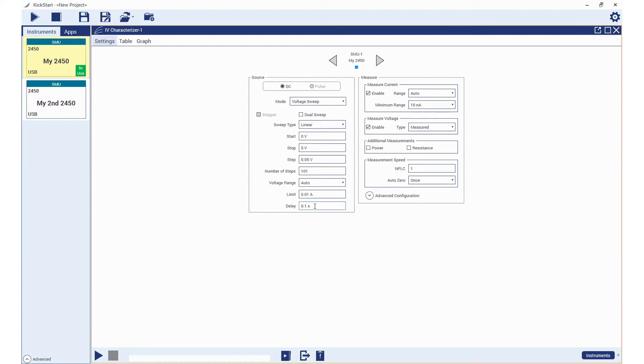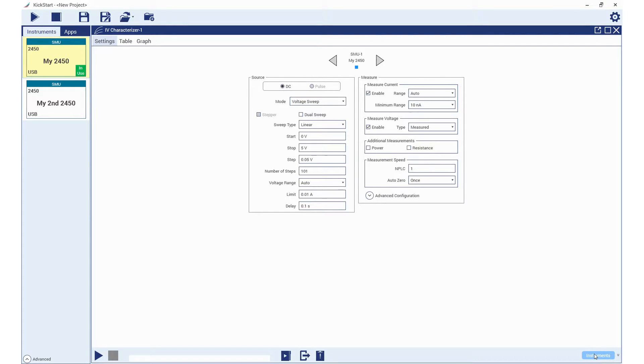We will now add the second SMU by clicking on the instrument icon at the bottom right-hand of the app window and use the add channel to add the second channel for this test.